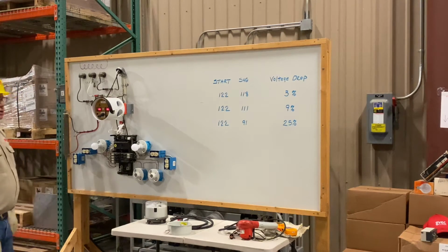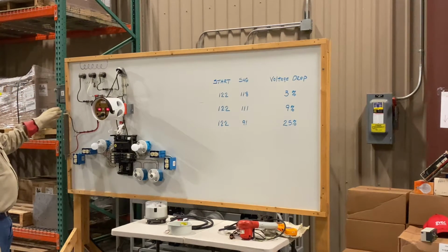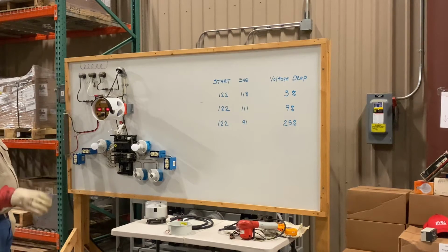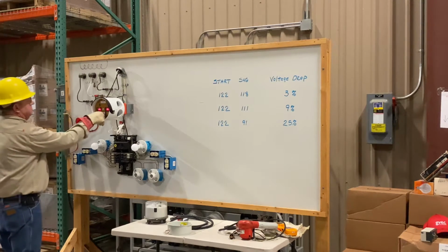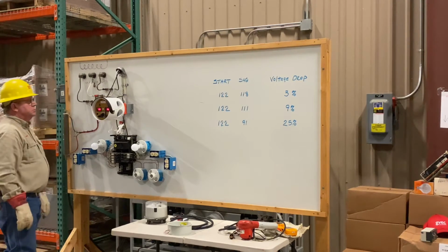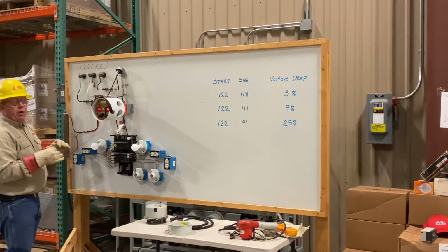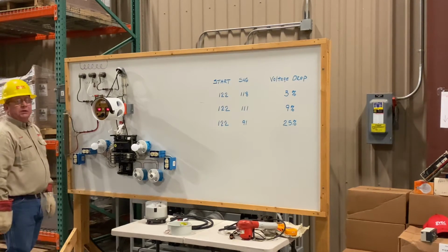We watch the voltage fall to 91 on the loaded leg, and it rises to 148 on the unloaded leg. We turn the load off so that we have 0 amps. We go back to a balanced voltage.